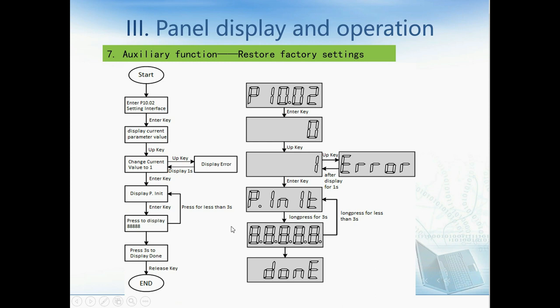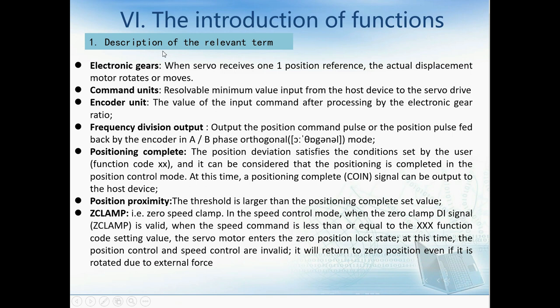In this chapter, there are some relevant terms for the servo drive. The first is the electronic gear: when the servo drive receives one position reference, it defines the actual displacement the motor rotates or moves. The second is the command unit — the resolvable minimum value input from the host device to the servo drive. The encoder unit is the value of the input command after processing by the electronic gear ratio.